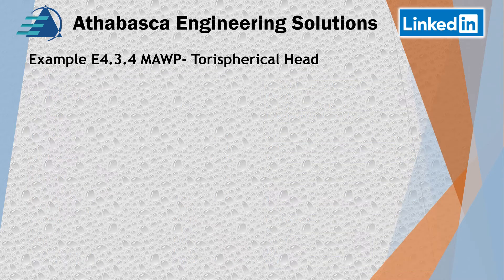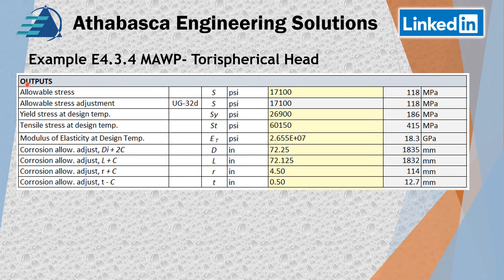We continue with the setup, pulling out the allowable stresses, the yield stress, and the tensile stress because we have to check our tensile strength is less than 70 KSI — and in this case we don't have to make any adjustments. Then we take the elastic modulus of the material from the code. We make our traditional adjustments for corrosion allowance where the inside diameter plus two times the corrosion allowance gives us the corroded final condition, and L is adjusted for corrosion allowances as well.